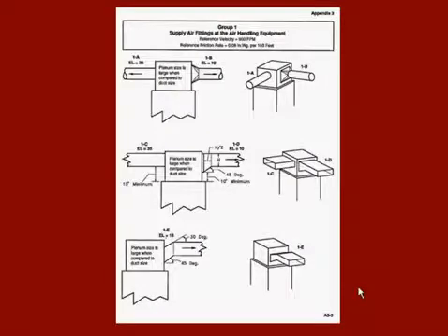Okay, in the back of Manual D, starting in Appendix A, in fact this is page A3-3, you will see equivalent lengths for fittings. For instance, let's just jump right into this. Take this connection here where we have a round piece of duct coming off of a supply plenum.